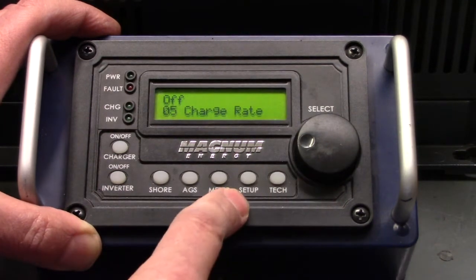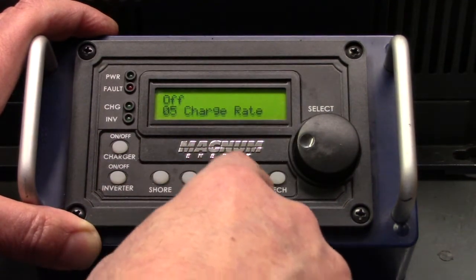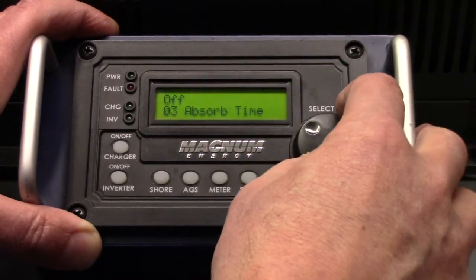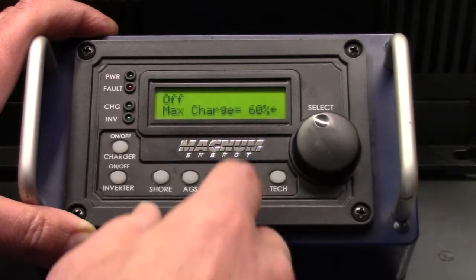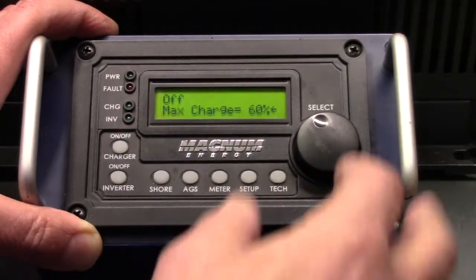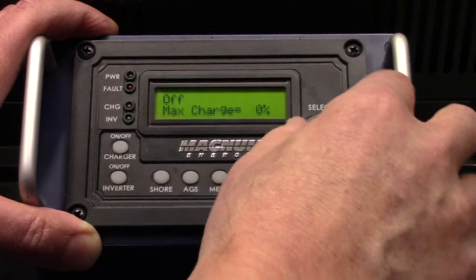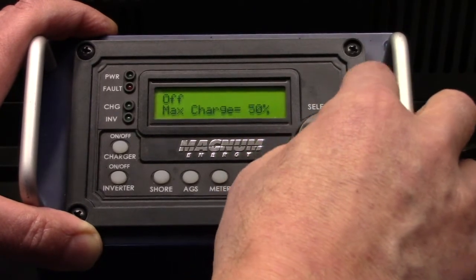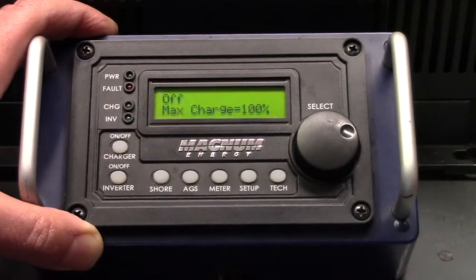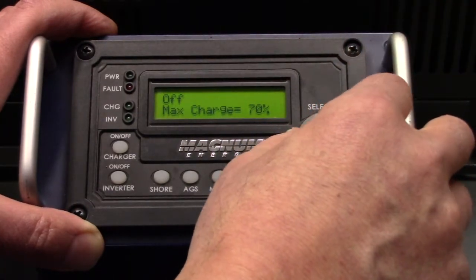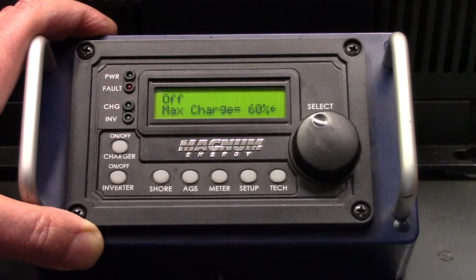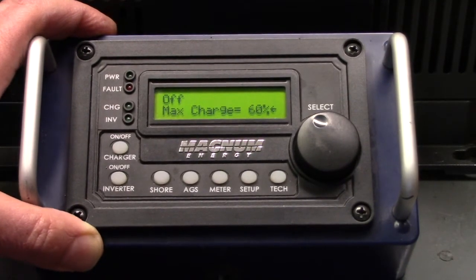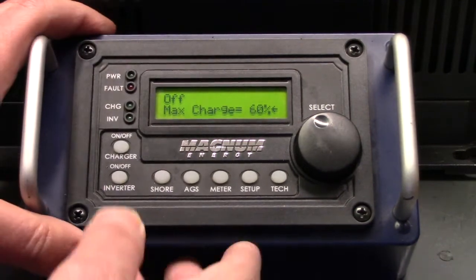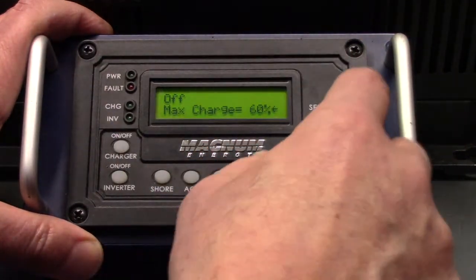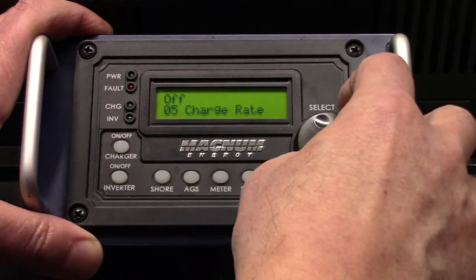You've got all day to let it charge, so lower the rate. You could just leave it at that lower rate forever, and the only time I'd change it is if you pull in somewhere and really need those batteries charged up in a hurry — then you can bump this up, all the way up to 100%, in which case it'll put over 100 amps into the batteries. So the factory default is 80. If you're not in a hurry to charge your batteries, I wouldn't put it higher than 60. Just let them take their time charging — it'll keep the unit running cooler, it'll be easier on the batteries, and it'll still get charged.